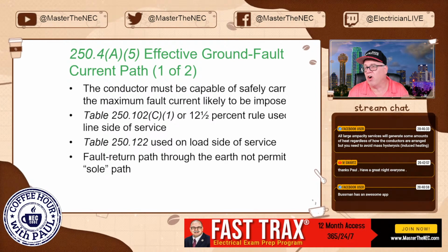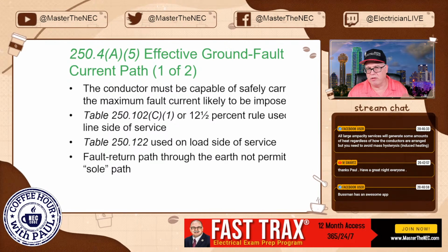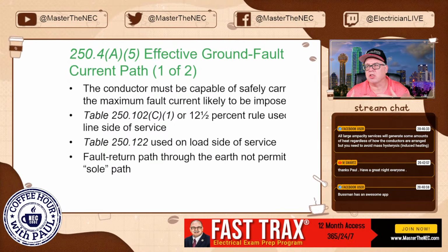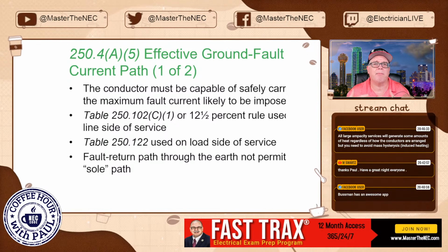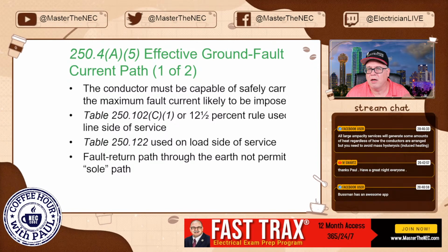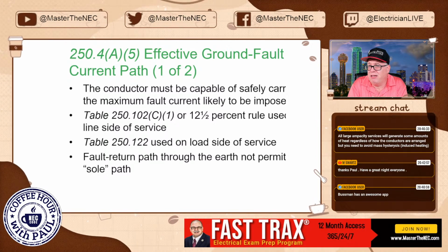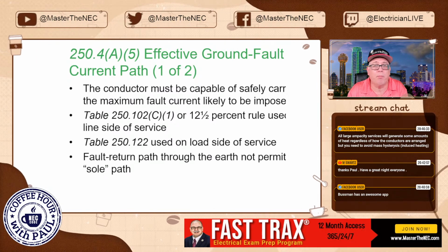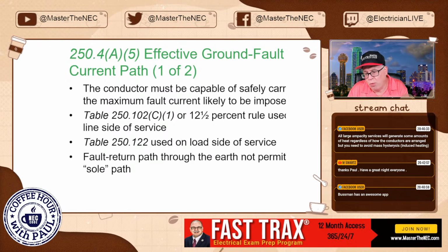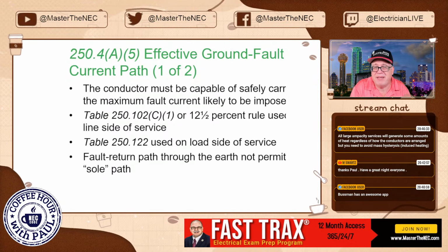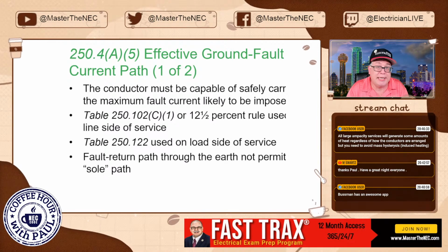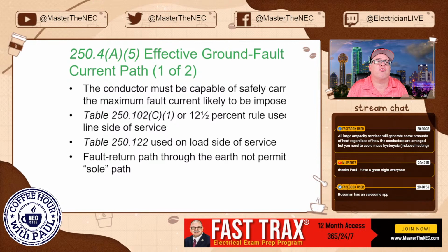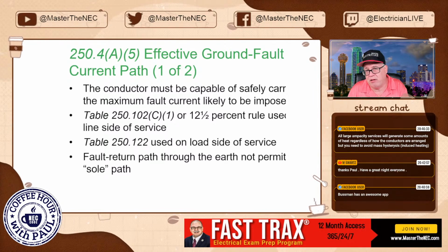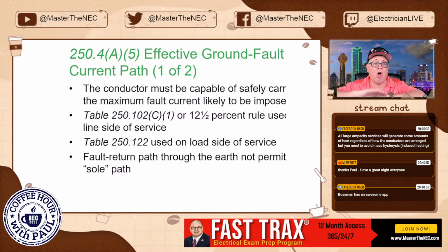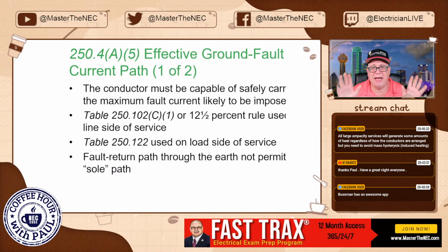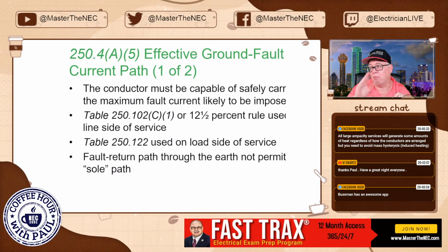Now, you heard that old saying? I'm sure you've heard this, fault current takes the path of least resistance. Well, that is kind of true. It takes all available paths proportional to the path with the least amount of impedance, okay? So that's why we construct a really good low impedance path. The majority of it will travel on that than it will on the high impedance path, okay? But it takes all paths, right? All paths. It doesn't just go, oh, I don't want to go to you.